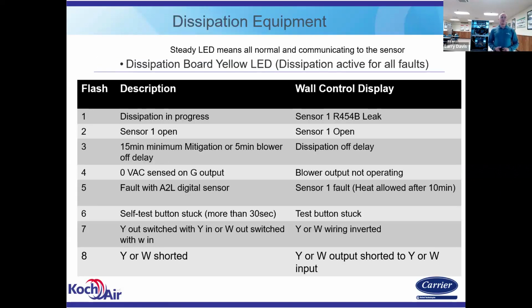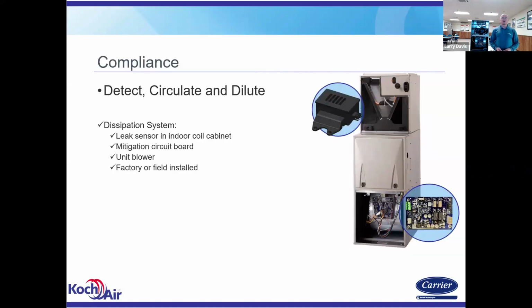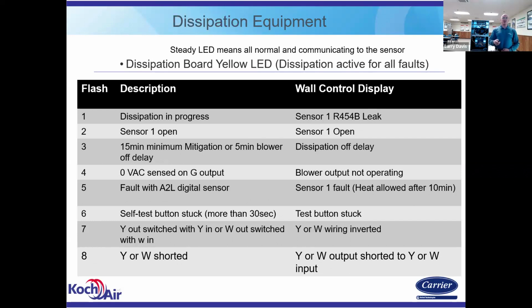Again, here are your fault codes for the dissipation board. This label should be on that board cover. There are two LEDs on there. One is the yellow one, that's your status. And the other is a green one, that's the communication. The green one only lights up if you're using the communication connections.